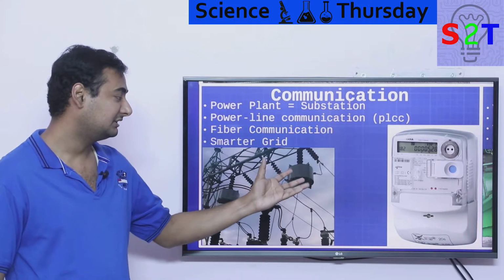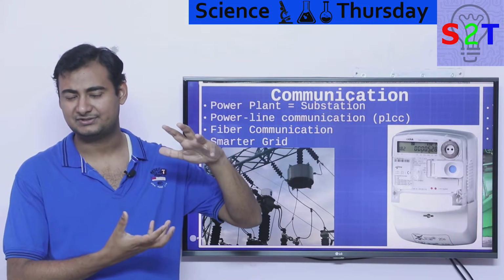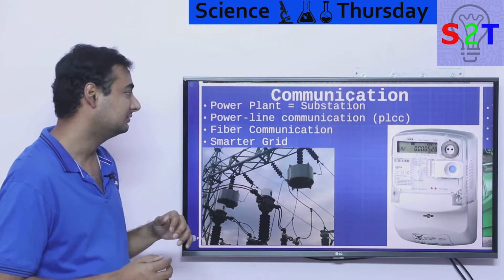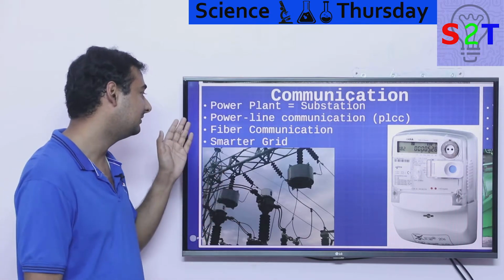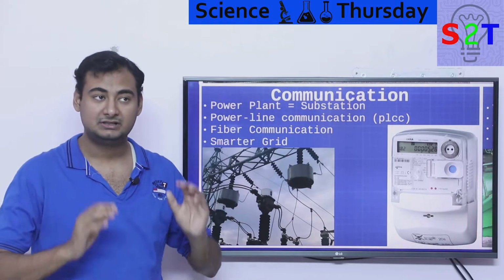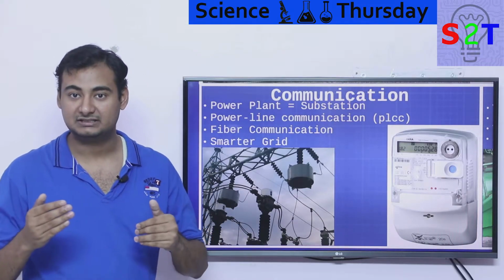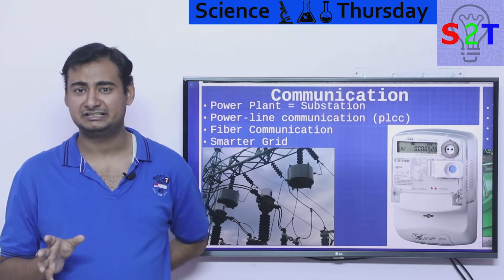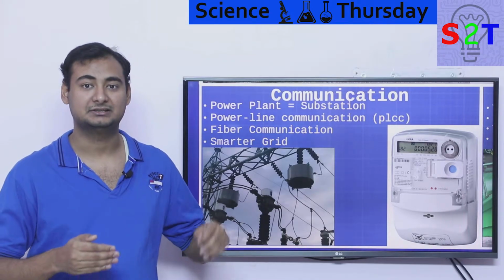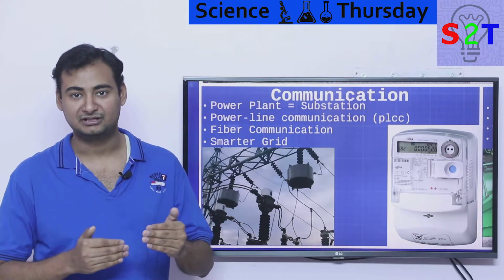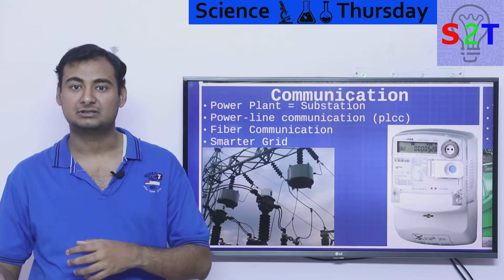If you see something like a big hanging mass on an old substation, that's what we call a wave trap. In earlier days we used power line communication. The high voltage line that goes to the substation itself used to carry a signal, basically a dial-up kind of connection, about 9 kbps, telling the system, okay, my load is 80 megawatts, 90 megawatts. Using that information, computers were controlling the output.